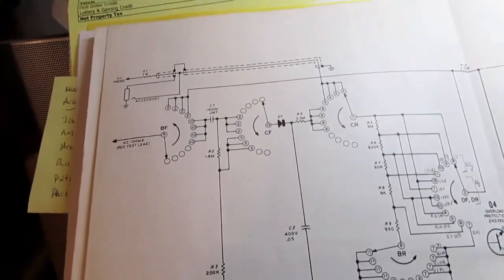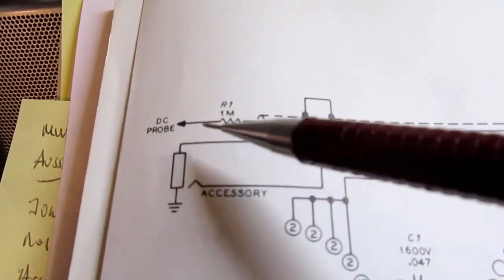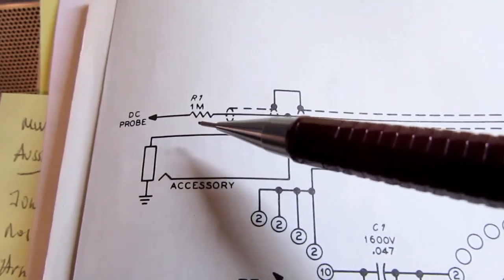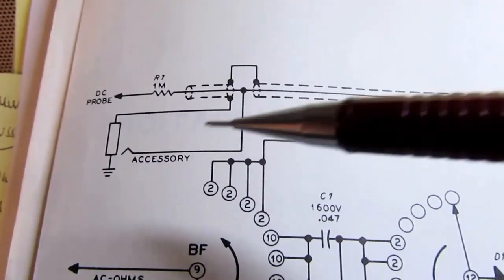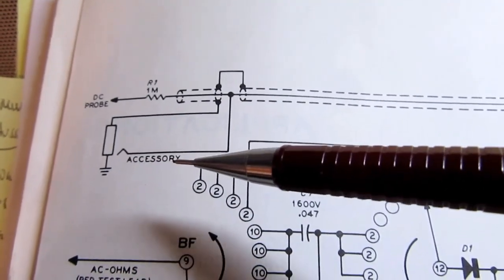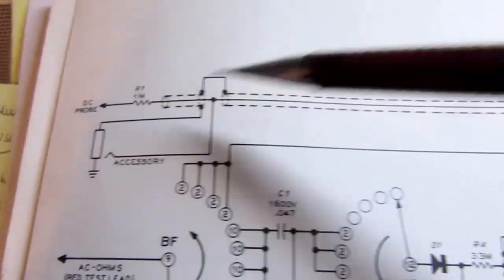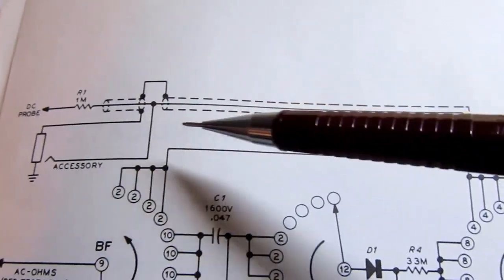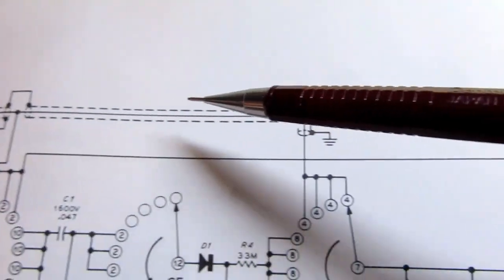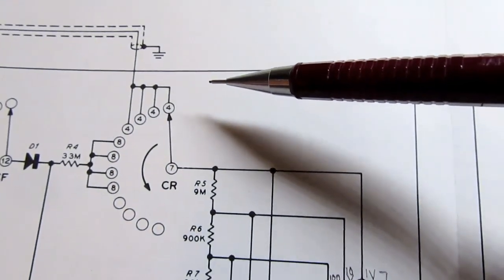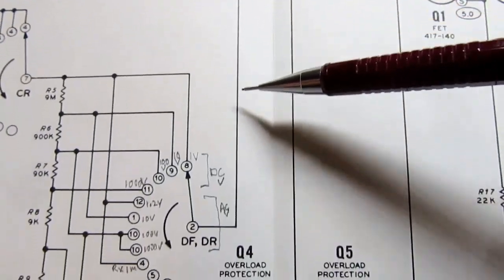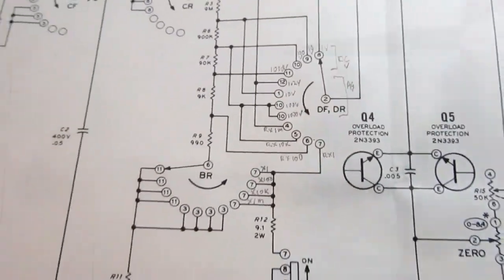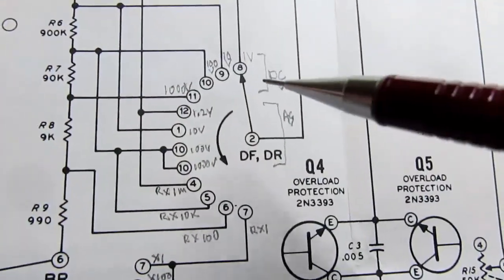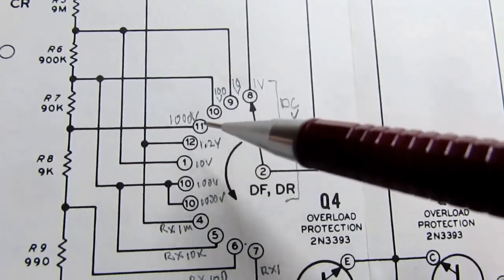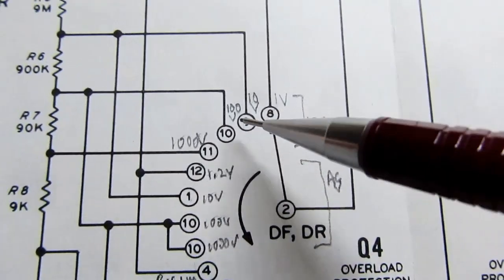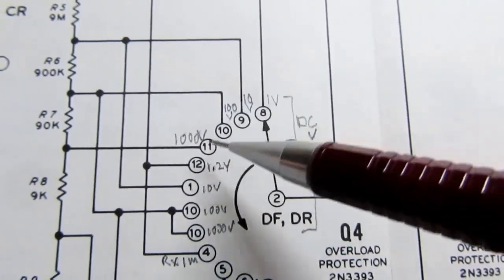Let's look at the front end of the circuit, and let's start with DC volts. The DC probe has a 1 meg ohm resistor built into it, and if you connect the accessory probe, either the high voltage one or the RF one, it's designed to act like this probe as far as the rest of the meter is concerned. So it's just wired in parallel. So you come over here with your DC voltage, and it goes right across here, and it's applied to this big range switch here. And depending which position it's on, let's take a look at the way I've got it marked up here. There's only 4 ranges for DC volts. The 1 volt range, the 10 volt range, 100 volt range, and 1000 volt range. So it's going to be one of these 4.